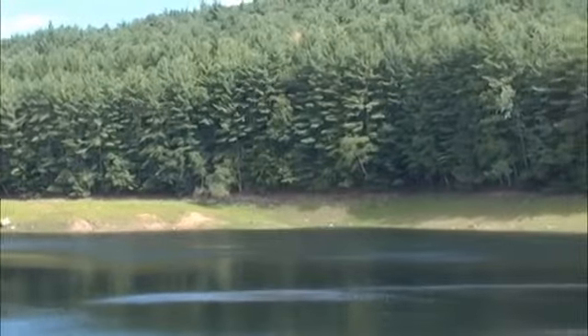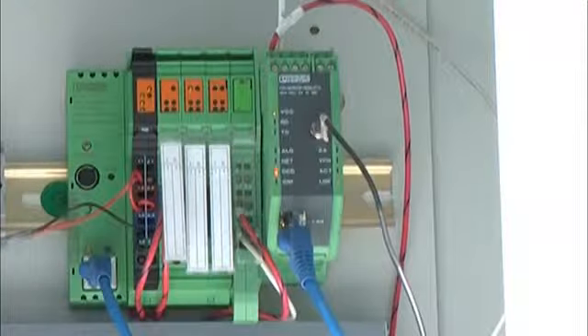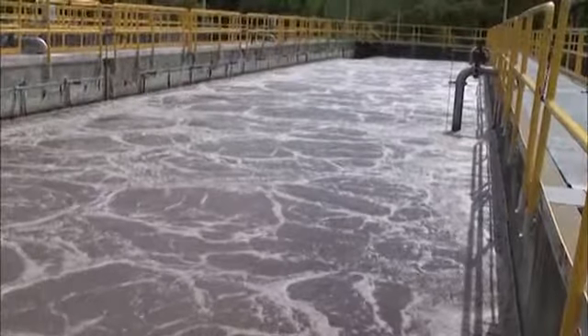The city's water reservoirs are located several miles from the control center. Because the signal from a traditional Ethernet radio would not travel the required distance, the city installed GSM GPRS Ethernet modems at the reservoirs, which could communicate over the cellular network. The local ILC controllers monitor water levels, then report any unusual conditions via the modem over the cellular network. The modem sends updated level and alarm information to the central SCADA system at the facility's headquarters, where the master control system activates the necessary process control systems.